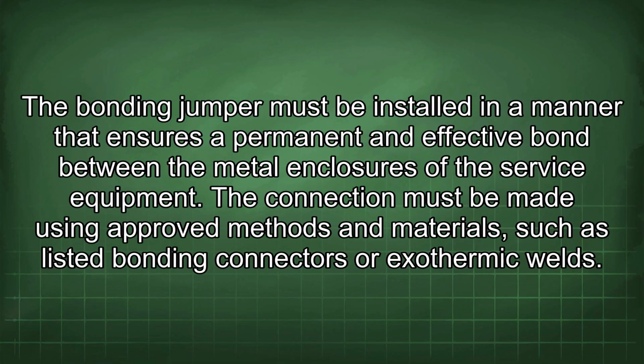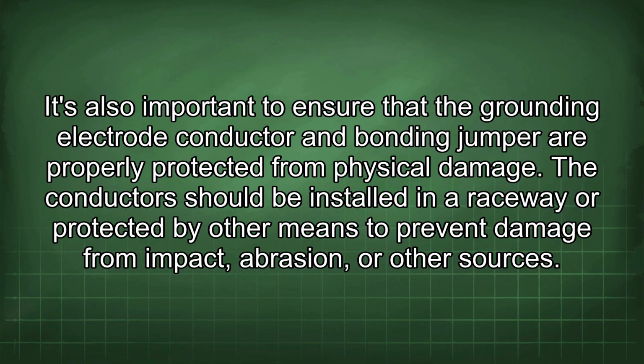required. The bonding jumper must be installed in a manner that ensures a permanent and effective bond between the metal enclosures of the service equipment. The connection must be made using approved methods and materials such as listed bonding connectors or exothermic welds. It's also important to ensure that the grounding electrode conductor and bonding jumper are properly protected from physical damage.